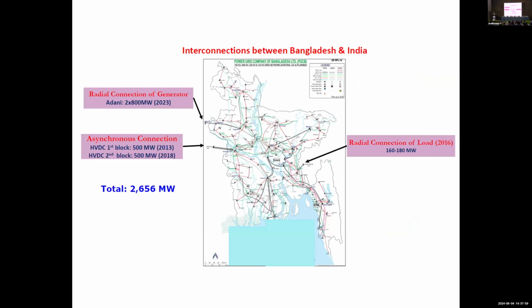Interconnection between Bangladesh and India: there's a radial connection of generation - we are importing power from Adani Power, radially connected to our grid, with total capacity of 1600 megawatts. We also have two asynchronous connections with India: HVDC block 1, importing 500 megawatts, and HVDC block 2, importing 500 megawatts. There's also one radial connection of load connected to the India grid, with 160 to 180 megawatt capacity. Total capacity of importing power from India is 2,656 megawatts.